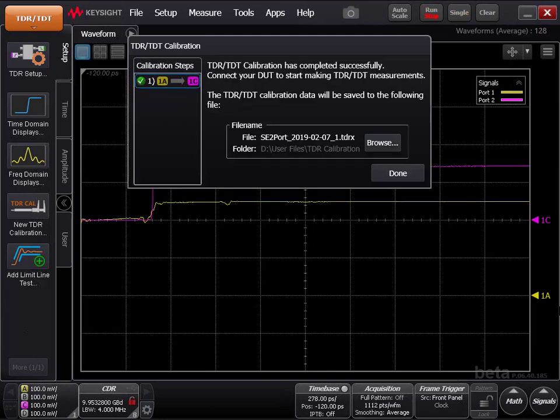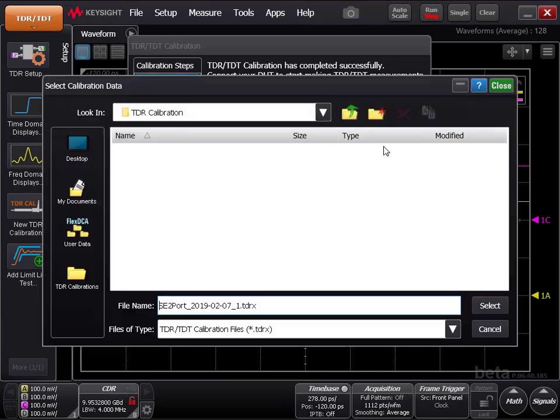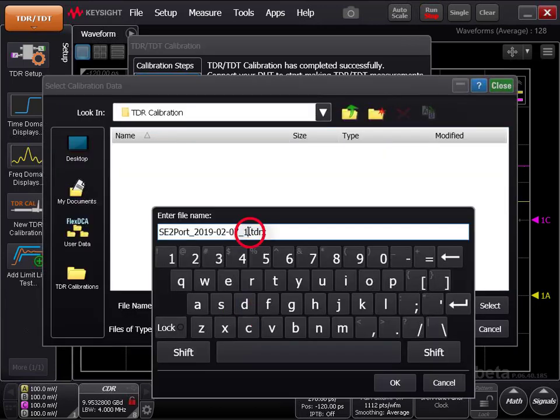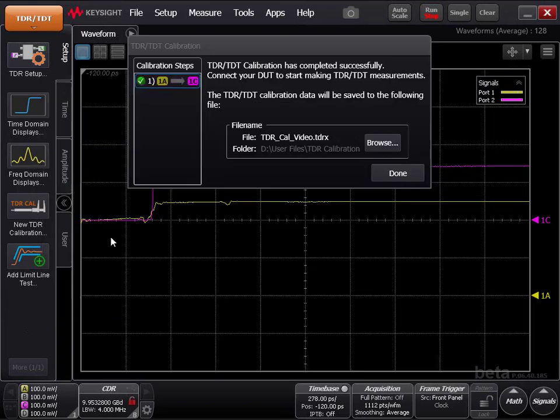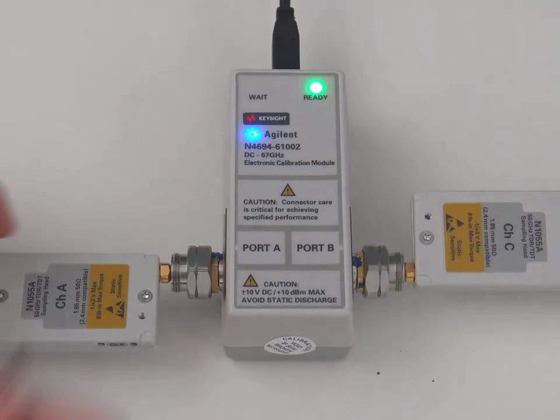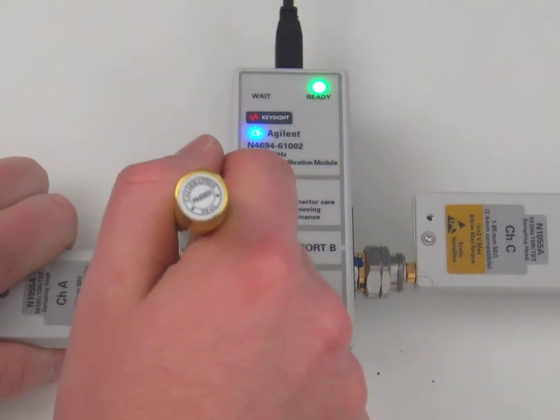When the measurement calibration is complete, you will be asked where you want to save the calibration file. Click Browse. Navigate to your preferred location and give the file a descriptive name. Click Done and remove the measurement heads from the ECAL module.